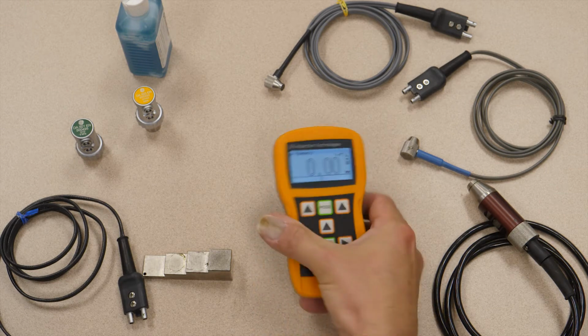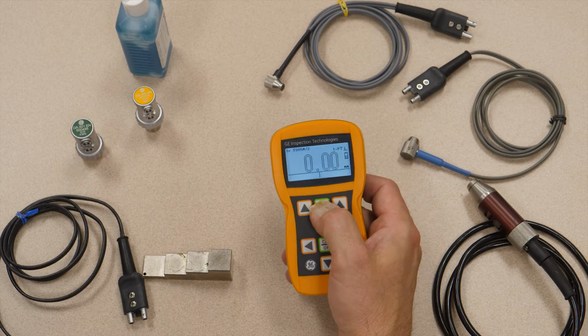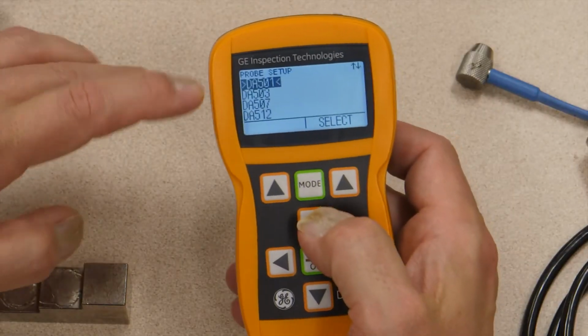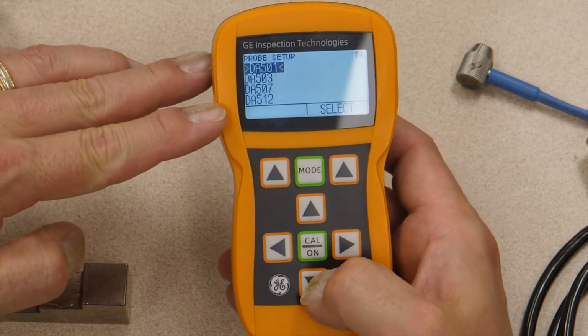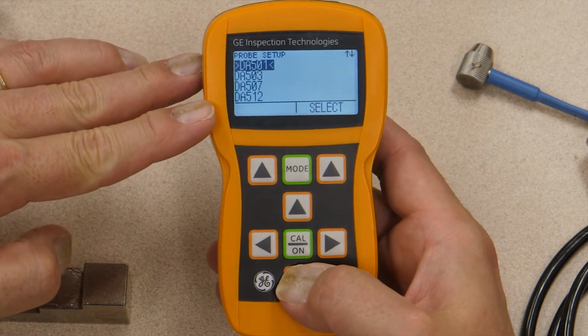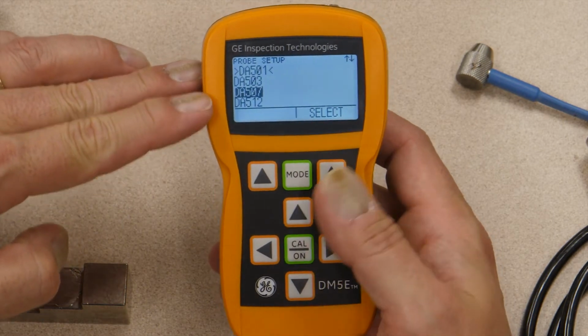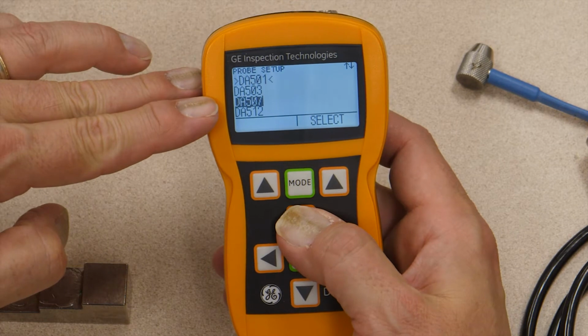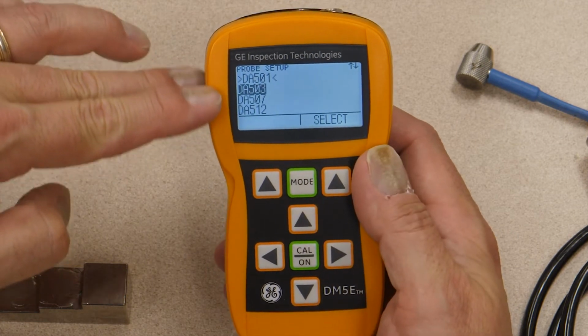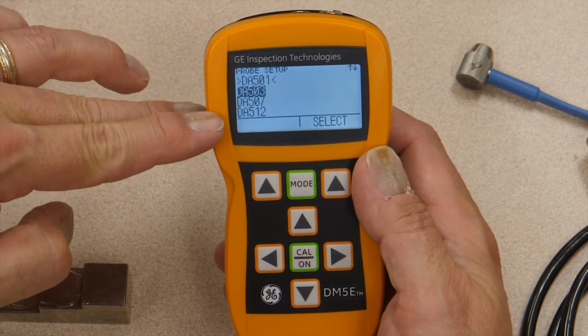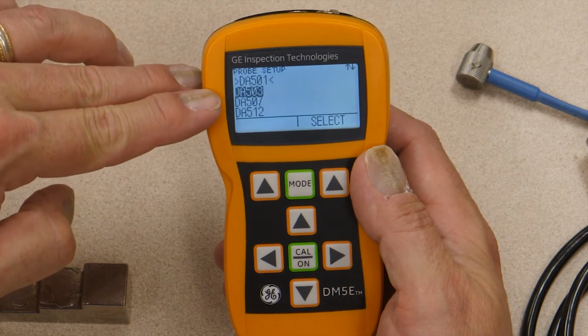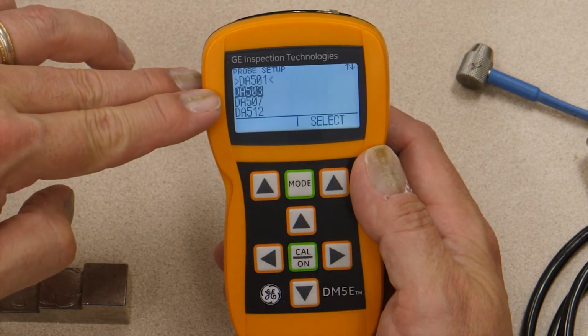So to do that, you have the instrument running, press the mode button, and it brings up the list of available probes, or the list of supported probes. You can scroll up and scroll down. You notice there's a black cursor. As I use the up and down keys, I can move through the list and the black cursor follows. The black cursor is not telling me which probe is currently selected though.